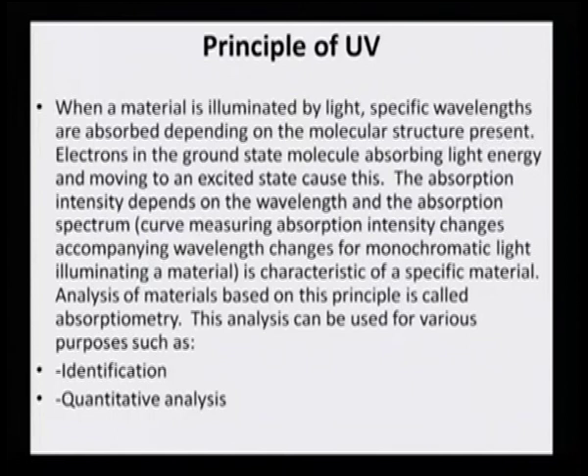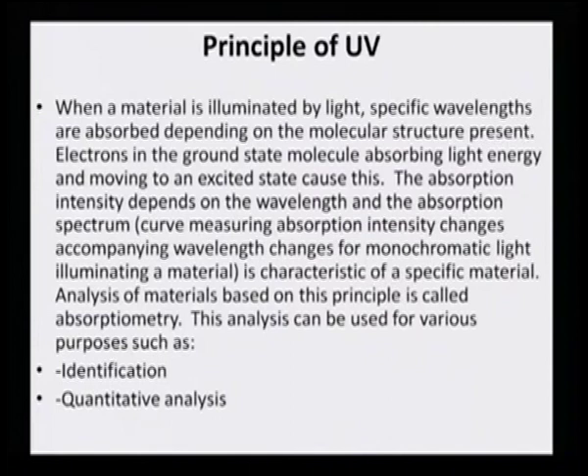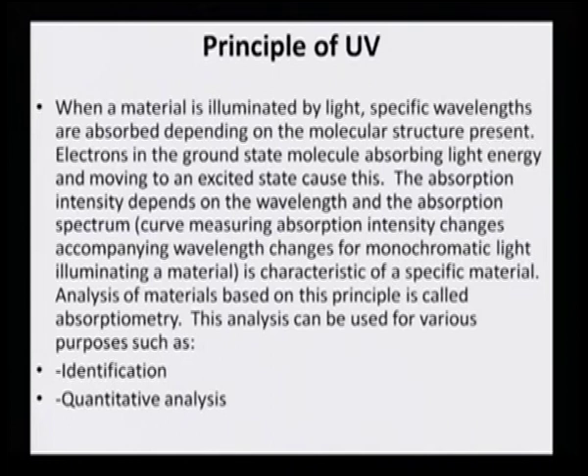Principles of UV: when a material is illuminated by light, specific wavelengths are absorbed depending on the molecular structure present. Electrons in the ground state molecule absorb light energy and move to an excited state, causing this absorption. The absorption intensity depends on the wavelength, and the absorption spectrum — the curve measuring absorption intensity changes accompanying wavelength changes for monochromatic light illuminating a material — is a characteristic of a specific material. Analysis based on this principle is called absorptiometry.